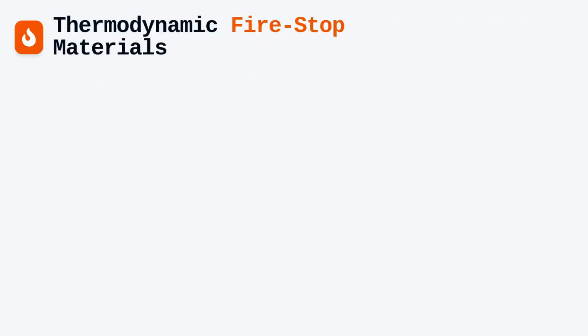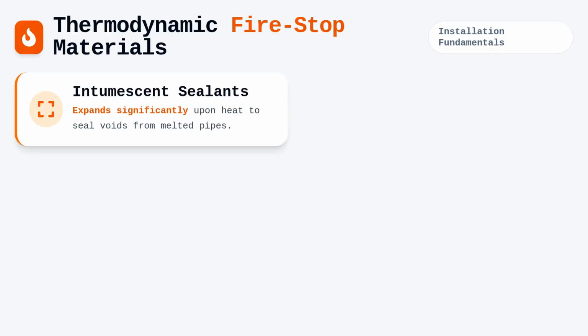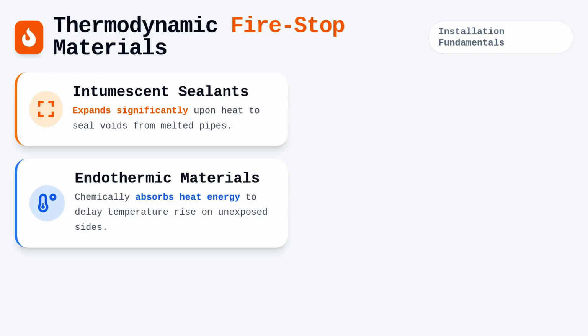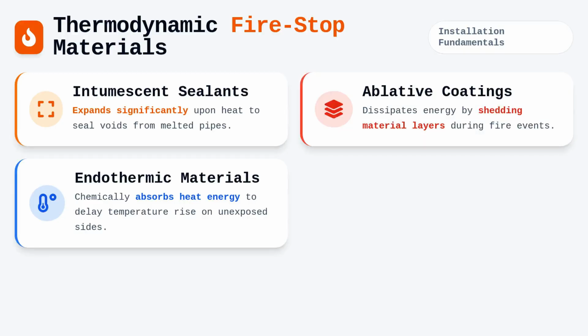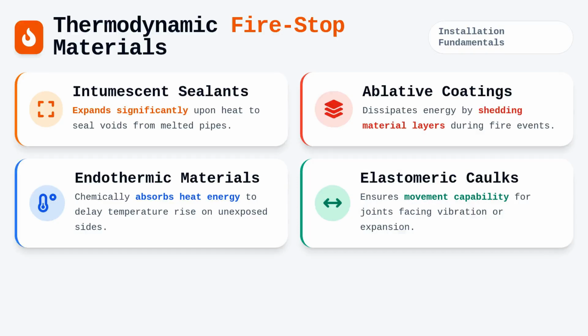The materials we use are engineered to respond to fire under distinct thermodynamic principles. Intumescent sealants are perhaps the most common, designed to expand significantly when exposed to heat. This expansion seals the void left behind by combustible service pipes that have melted away during a fire event. You must distinguish these from endothermic materials, which chemically absorb heat energy to delay the temperature rise on the unexposed side of the barrier. Ablative coatings, on the other hand, function by shedding layers of material to dissipate energy through ablation, while elastomeric caulks provide the necessary movement capability for joints that must withstand thermal expansion or structural vibration.